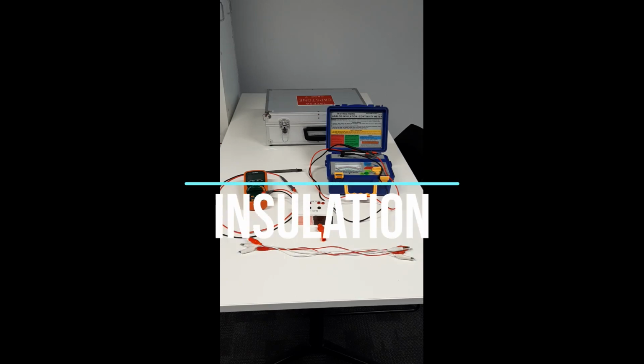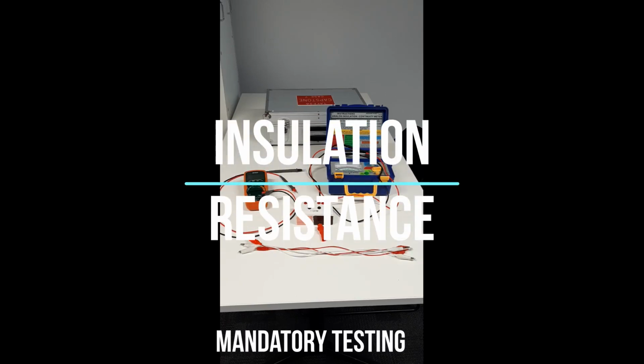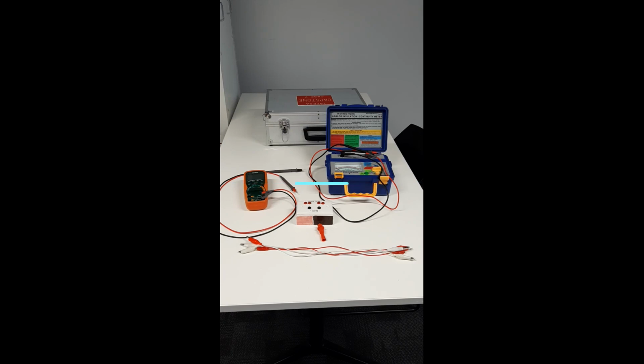This video will demonstrate how to perform the insulation resistance tests. This test is performed on the whole installation, the consumer mains and the submains to save time, but a low result means the circuits must be tested individually.